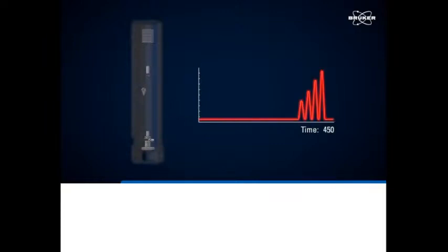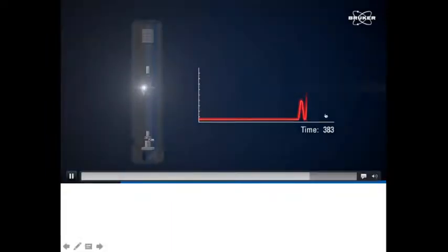The ions travel via the reflector towards the detector, and thus a TOF spectrum is recorded. The detection of the selected precursor ion and its fragments creates a TOF spectrum. Whether fragmentation occurs through higher laser energies or a collision gas, the structural details derived from the MALDI-TOF spectrum provide a deeper analytical insight of the targeted compound.